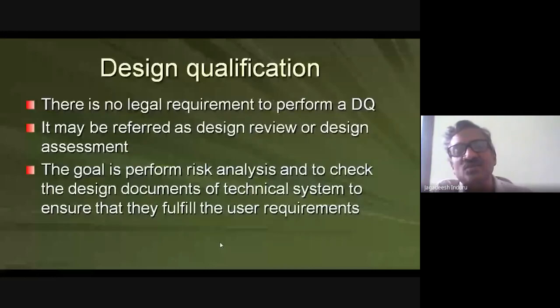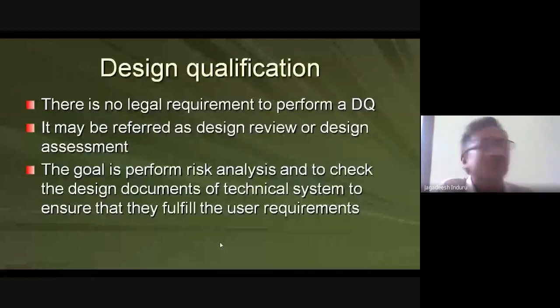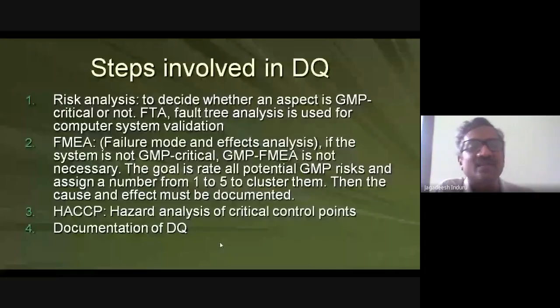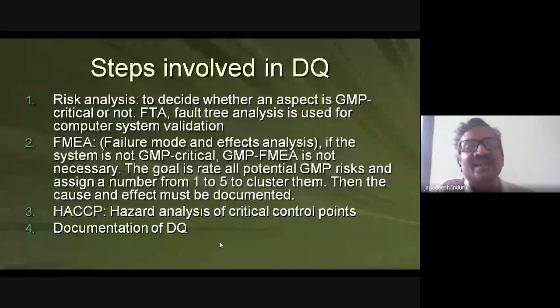The user — whether a patient, customer, or anyone providing funding — must be considered. The user requirement is the first step in the qualification process: how many patients, what is the batch size, is it a continuous or batch process. Accordingly the design qualification is drawn. Even though DQ appears to be a brainstorming session, it must be done critically. Just like before purchasing a mobile phone, you think about screen size, RAM, storage, pixels, and budget before going to the shop.